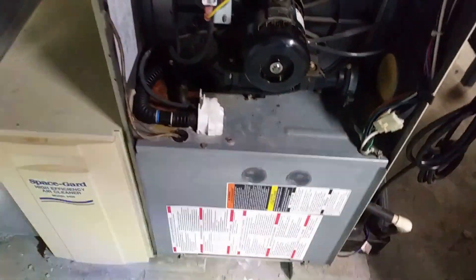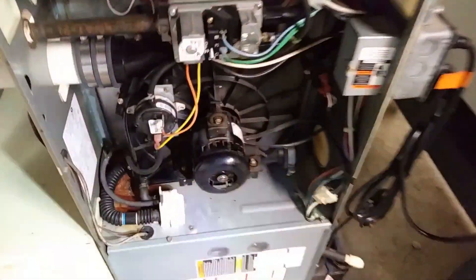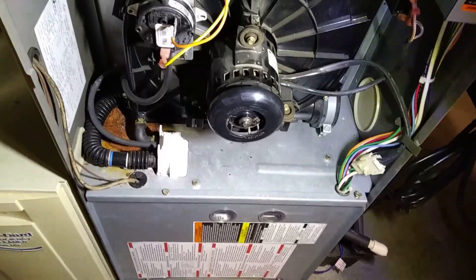So let's turn the power on. The main blower comes on, but the induction blower here — this thing is shot. You can feel it. But like I said, I just want to see if it'll spin up enough to throw some heat, and then we'll go from there.